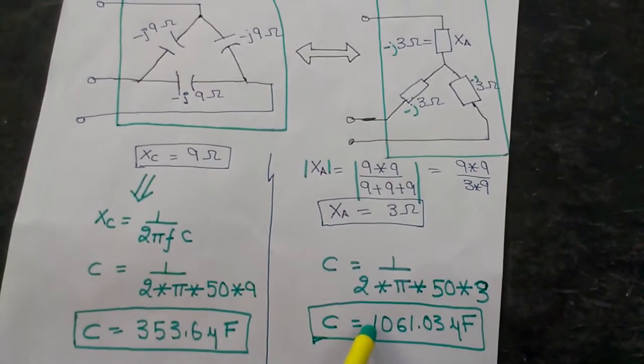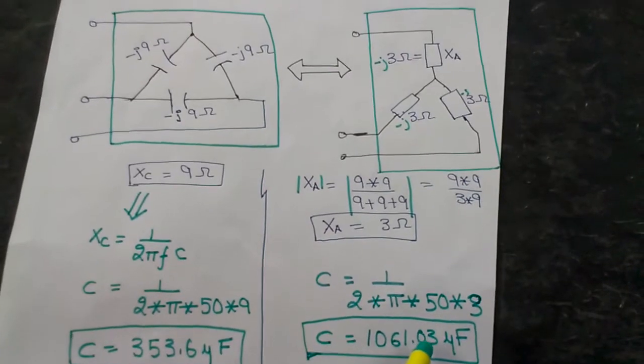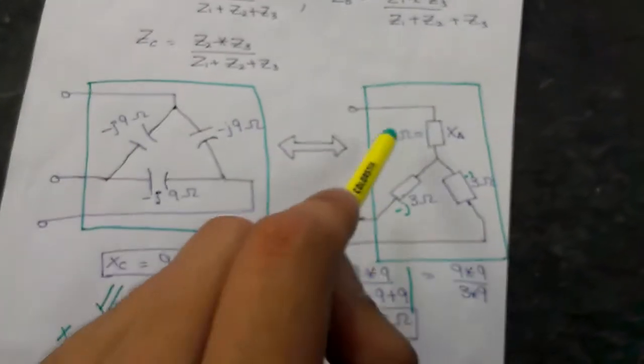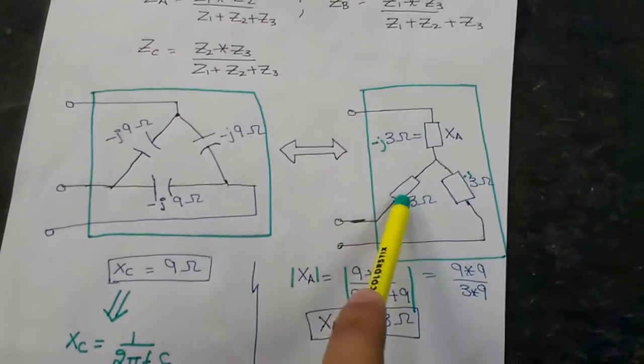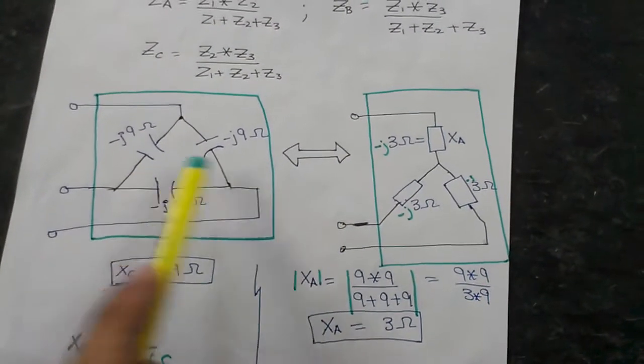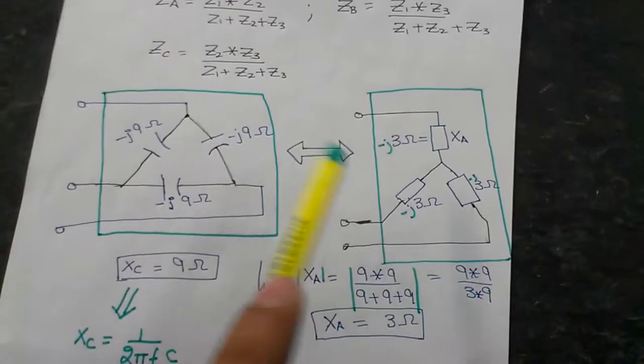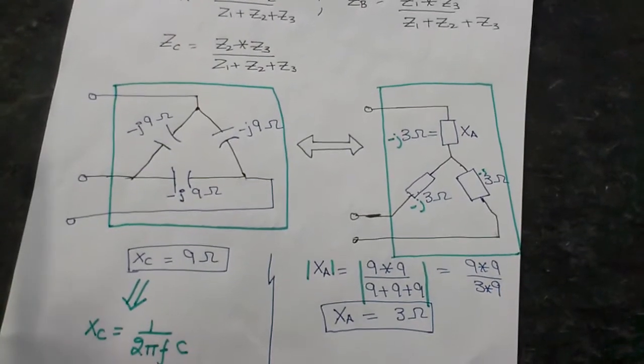That is, if you put the three capacitors in star configuration of 1061.03 microfarad and take the three terminals out and put this one also in a black box, you cannot differentiate these two black boxes in terms of the reactive power they are going to provide.